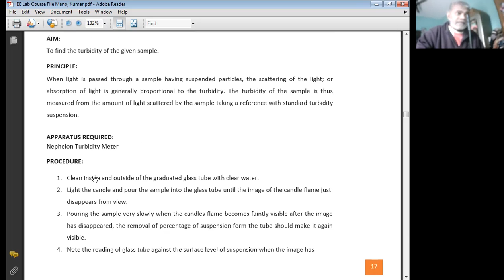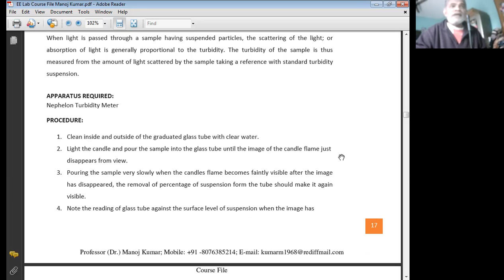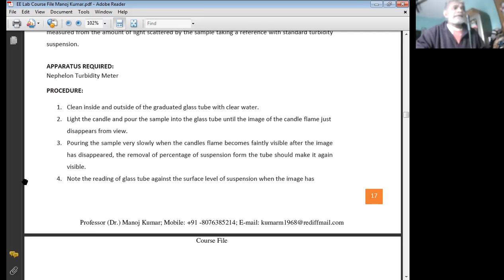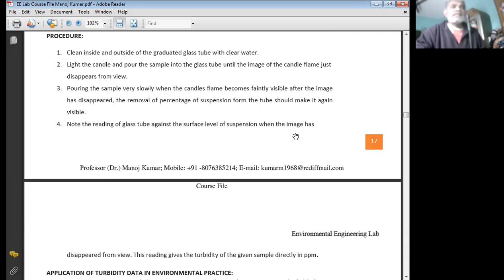Procedure: clean the inside and outside of the graduated glass tube with clear water. Light the candle and pour the sample into the glass tube until the image of the candle flame just disappears from view. Pour the sample very slowly when the candle has become faintly visible, until the image has disappeared. Note the reading of the glass tube against the surface level of the suspension when the image has disappeared from view. The reading gives the turbidity directly in ppm.